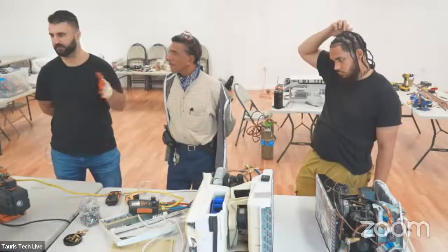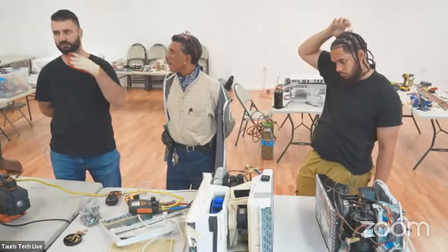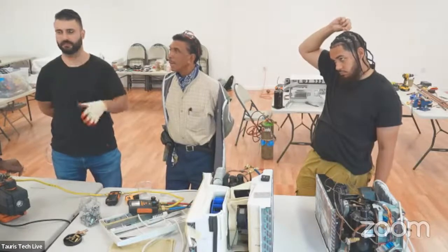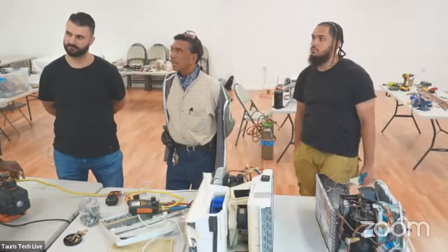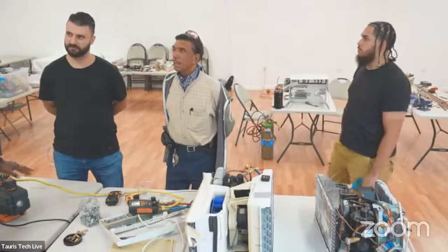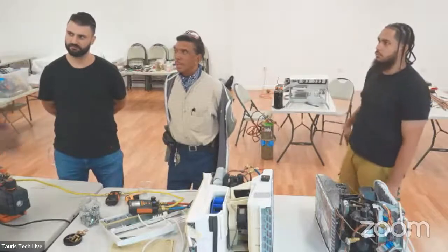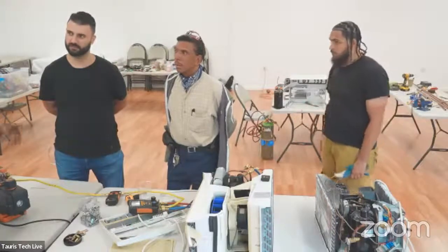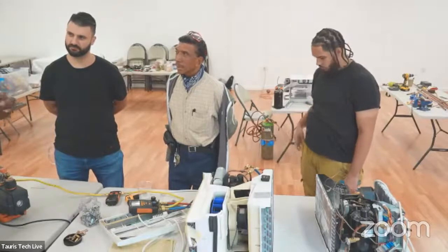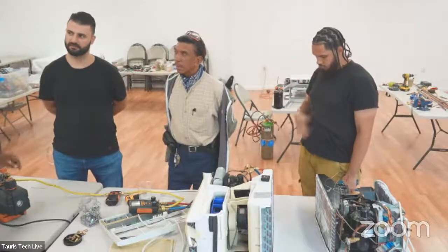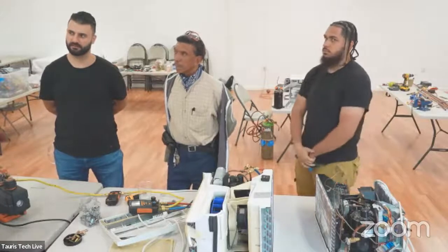They come and they put on all the suits and stuff. Oh, yeah. So if they were patching tubes, right? There's something called crystallization. Remember, I said that lithium bromide is what? It's salt water, right? So when it gets very cold, the salt crystallizes and it clogs up the tubes. And then they've got to come in.